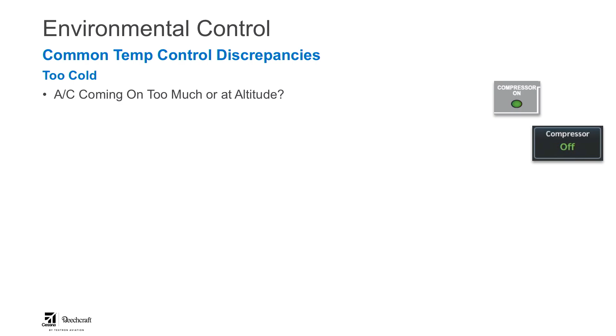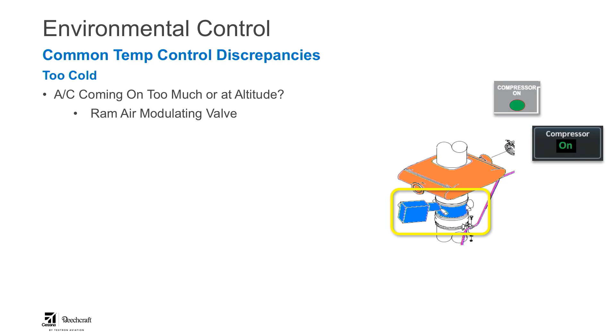That valve will trigger the air conditioner to come on when it's fully open, and it will stay running until it reaches the halfway closed position. So if it's on all the time, for some reason that valve is open. It could be the valve itself, or it could be a sensor or something else.